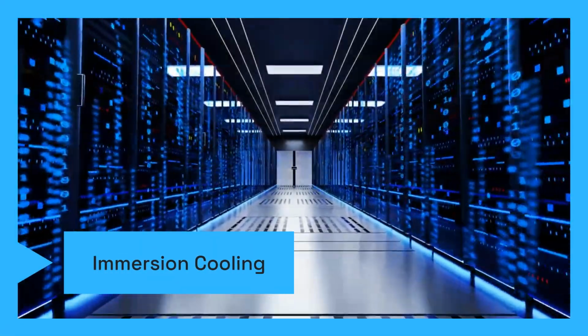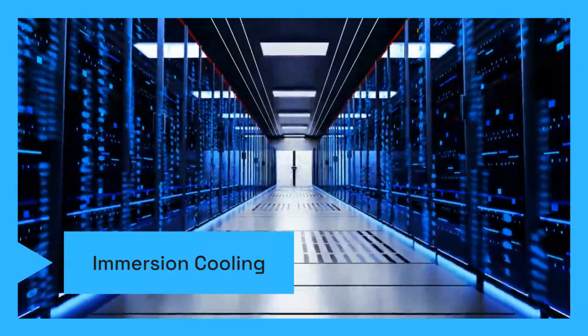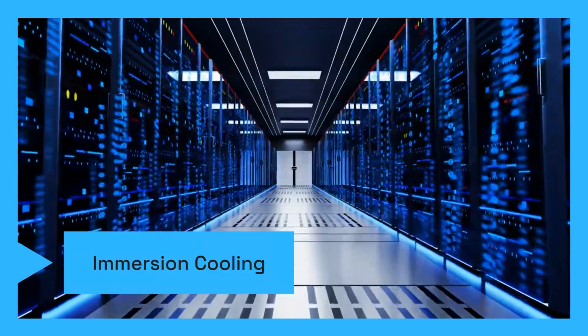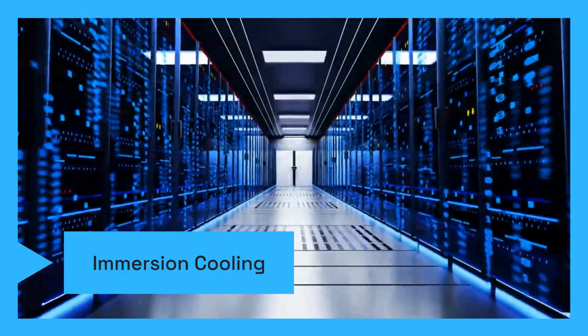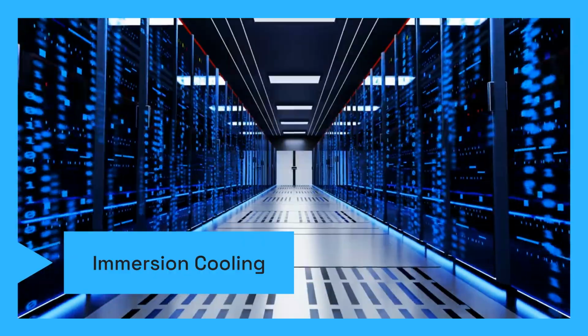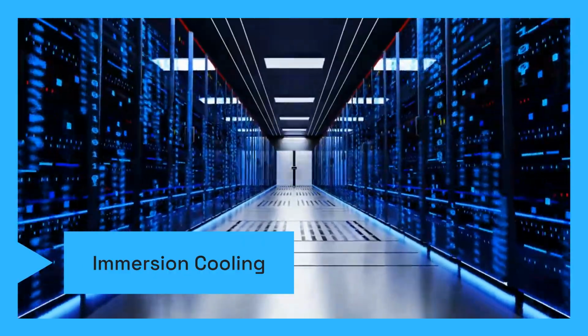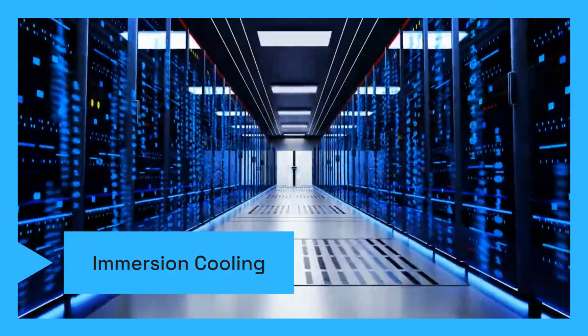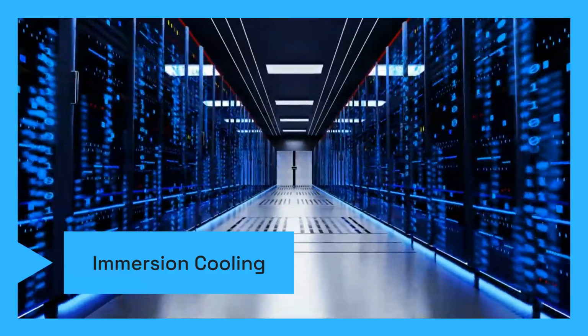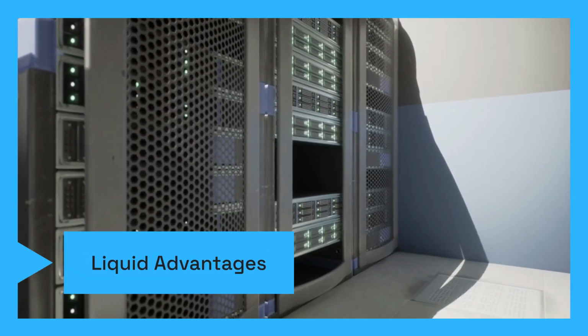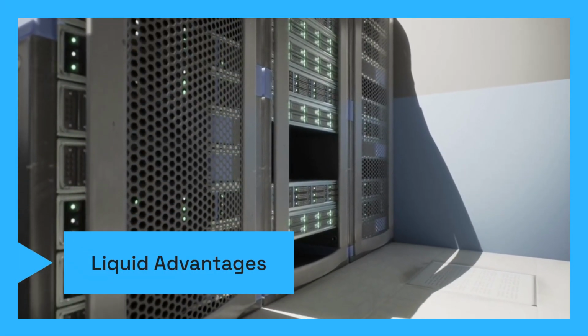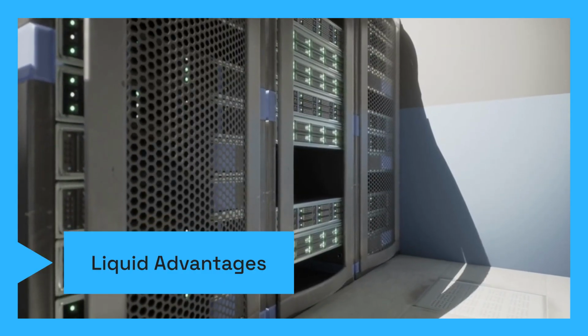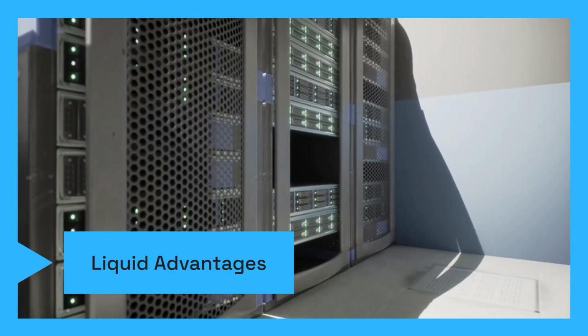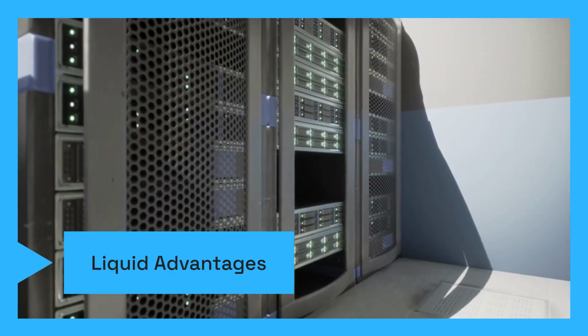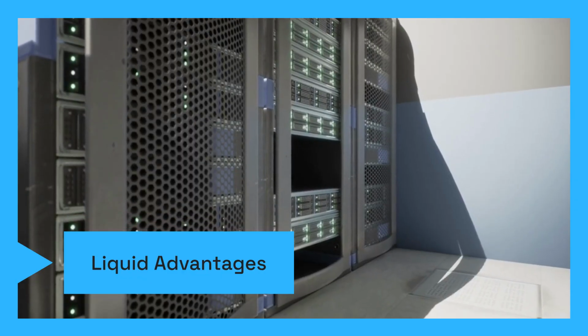Immersion cooling takes it a step further. Entire servers are submerged in a non-conductive dielectric fluid. This can be single-phase, where the fluid is pumped and cooled externally, or two-phase, where the fluid boils and condenses, creating a passive cooling cycle. It captures nearly 100% of IT heat. Liquid cooling offers superior energy efficiency, enabling extreme rack densities exceeding 100 kilowatts. It optimizes space, enhances performance by preventing thermal throttling, and operates much quieter.